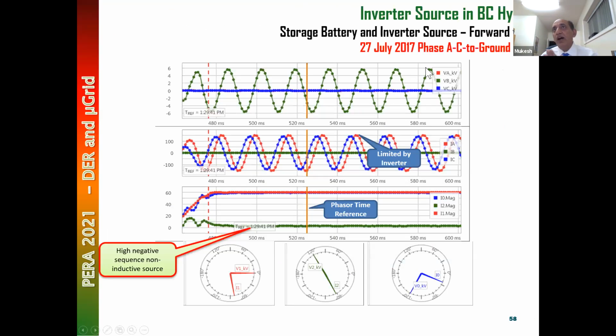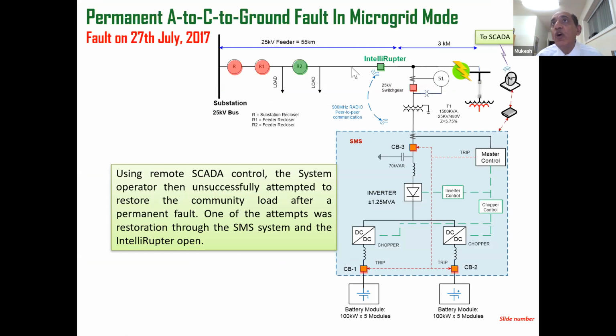Now, I wanted to come back and tell you why it cannot see a reverse fault. We actually had a situation. We had a permanent fault here. The fault happened, this recloser opened and this intelligent interrupter opened, and it was open for some time. Finally, the operator tried closing this one, and again it faulted. Because it was a forward fault, the intelligent interrupter did not go into microgrid mode. It said, no, I see a forward fault. Then I think the system shut down.